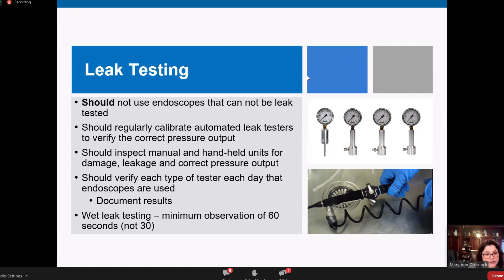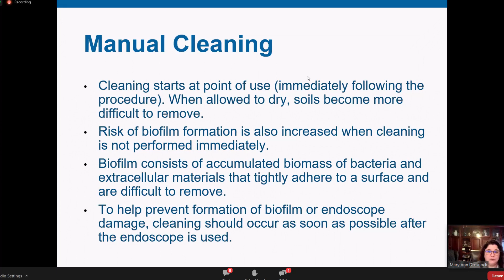As far as manual cleaning goes, we didn't put much more new in here because we really focused on that in the first ST91. We stated it's critical. It needs to be done immediately without time delay. We've discussed the delayed reprocessing procedure already, but as scopes sit and they're dirty still, they're still highly contaminated. You can have these biofilms start to develop, and then we don't know whether we can ever get those scopes truly cleaned, decontaminated, disinfected, or sterilized. So we have to make sure that we're avoiding this biofilm formation because it is very tightly adhered to the surface and extremely difficult to remove once it's there. And that's why we need to make sure the subsequent steps of endoscope processing are followed in order and without time delay as often as possible so that we don't have these biofilms start to develop.